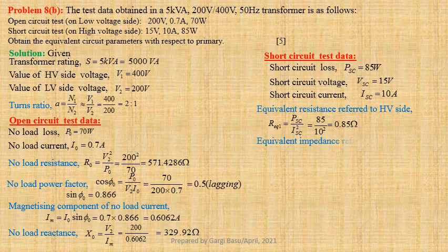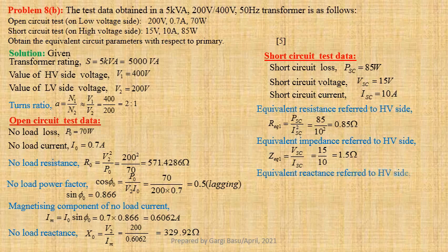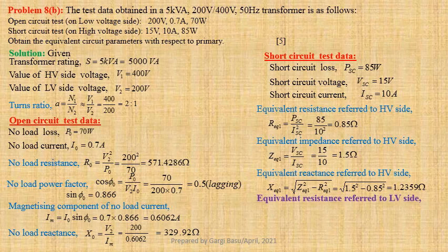Now we shall determine equivalent impedance referred to high voltage side. ZEQ1 equals VSC divided by ISC, that is equal to 15 divided by 10, that gives us 1.5 ohm. Now we shall determine equivalent reactance referred to high voltage side. XEQ1 equals root over ZEQ1 square minus REQ1 square, that is equal to root over 1.5 square minus 0.85 square, that gives us 1.2359 ohm.